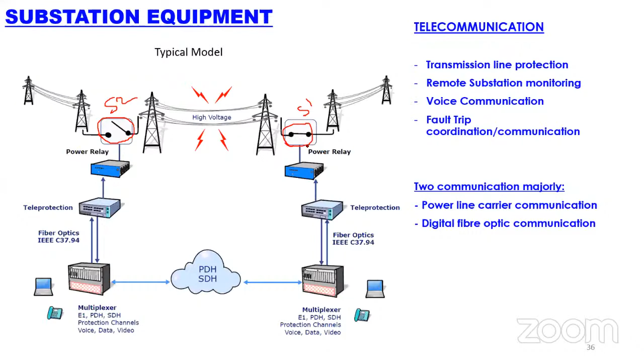For example, there is a fault in this high voltage line. What will happen? Let's take this as substation 1 and this as substation 2. Both substations have a breaker. The breaker will open by communicating the command signal from one end to the other, because substation S2 will communicate through fiber optic to the other station. So there is a fault, I have opened it, and that information goes to the opposite control system, which will take charge and may give a command to the relays.